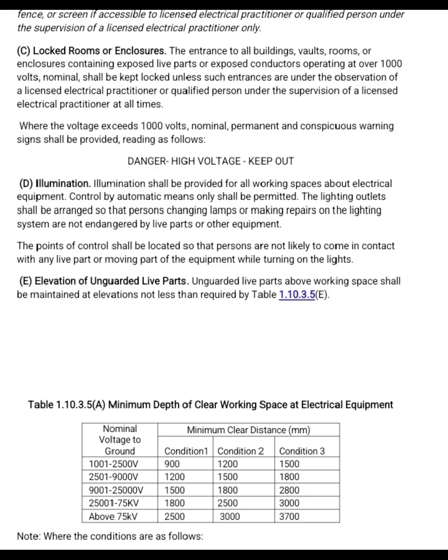D. Illumination. Illumination shall be provided for all working spaces about electrical equipment. Control by automatic means only shall be permitted. The lighting outlet shall be arranged so that persons changing lamps or making repairs in the lighting systems are not endangered by live parts or other equipment. The points of control shall be located so that persons are not likely to come in contact with any live part or moving part of the equipment while turning on the lights. E. Elevation of unguarded live parts. Unguarded live parts above working space shall be maintained at elevations not less than required by Table 1.10.3.5e.